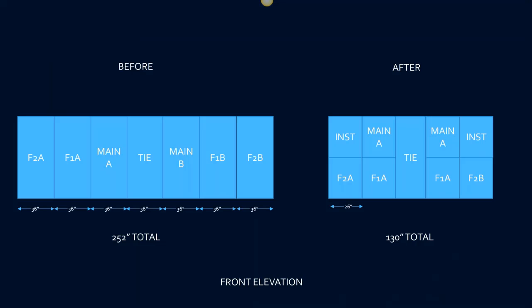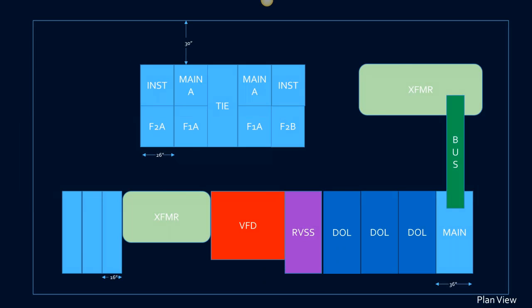And so let's look at what's happened to our lineup. We've taken our old traditional one high metal-clad switchgear. It's 36 inches wide, one high, and usually that means the breakers in the bottom, the instruments, and the relays are on the top section. And we have compacted things all the way down to 130 inches of linear width, and the depth being held constant. So that really has affected our room as well. I do want to point out up there that you do still need the 30 inches of clearance in the rear.